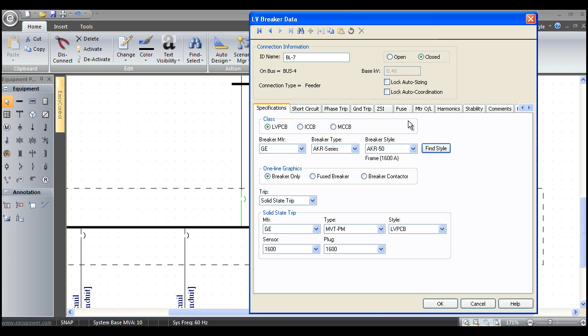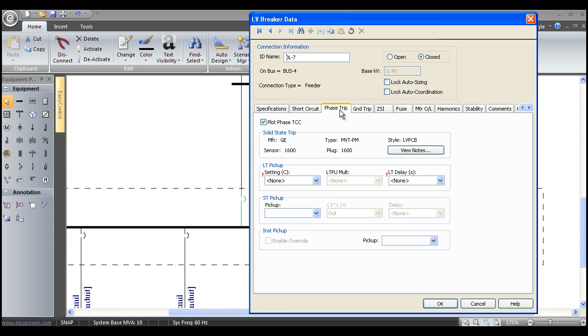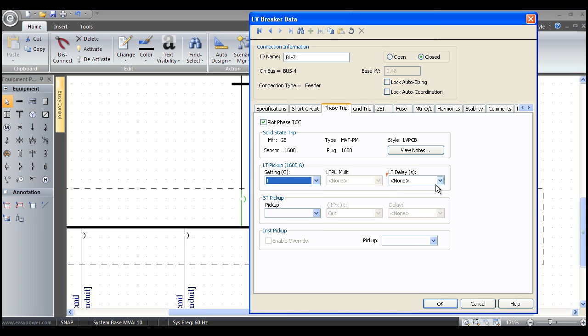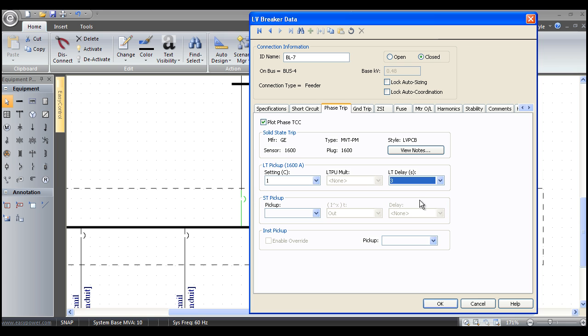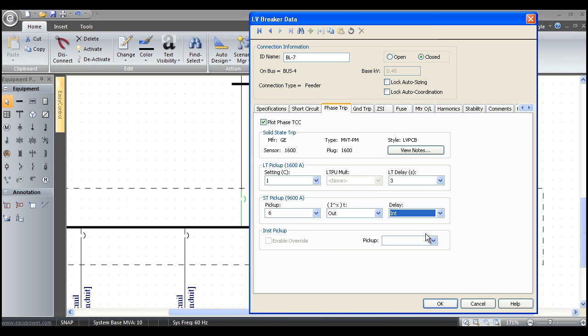Low voltage power circuit breakers have a lot of different tabs up here. We typically only use the first three for most studies, but we have a lot of different options in case you want to add other functionality. Short circuit—all we do is hit calculate, that tells us this breaker is rated for 50 kiloamps. The phase trip settings show us that once you put a sensor or trip device in, we need to know what the settings are. Now, if we were doing automated design, the automated design procedure would select all this for us, but now we're assuming that we're actually out collecting field data. So we'll put in the trip devices.